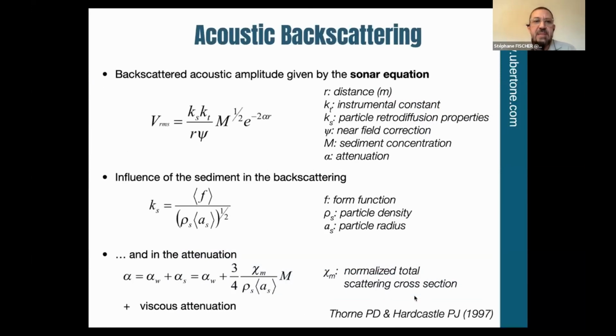Acoustic backscattering can be easily defined by the sonar equation. The sonar equation gives the voltage on the transducer as a function of the concentration, with a part that comes from the scattering of the particles, a constant from the transducers and from the system, and then attenuation. So here the exponential decrease refers to the attenuation.